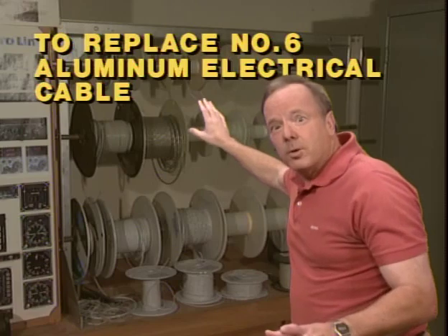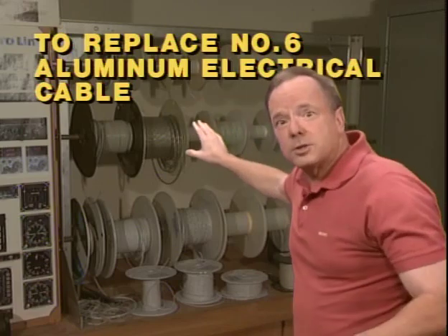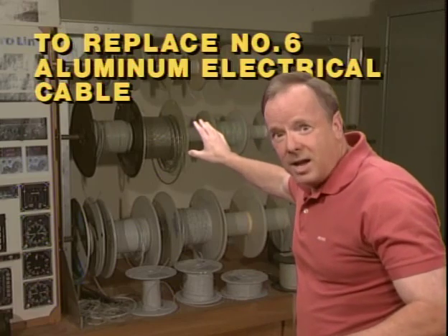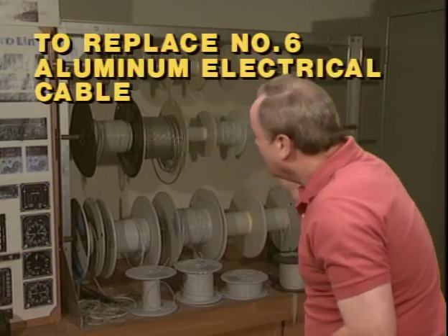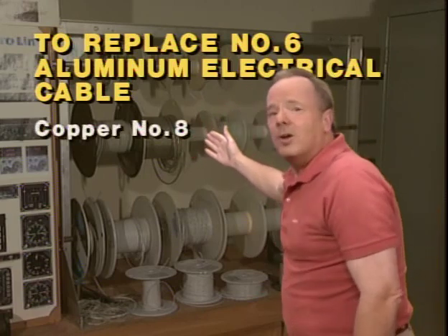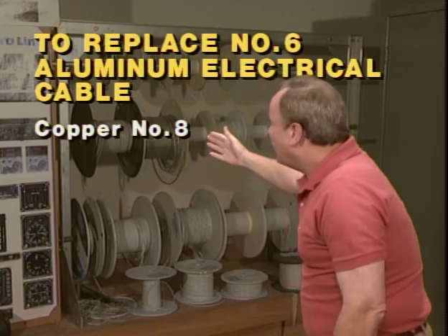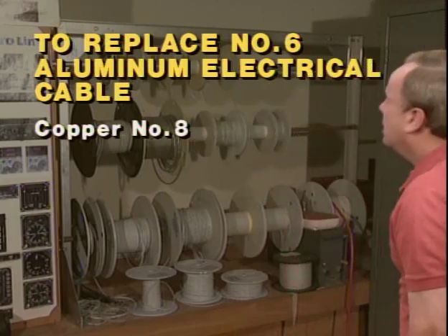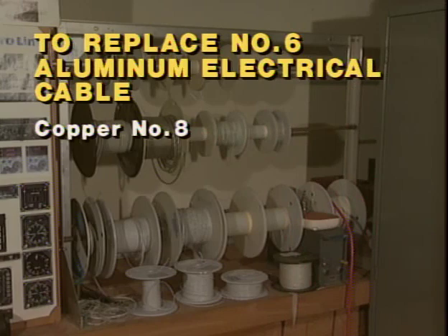Now, if you remember, you get to go 2 sizes smaller. That means you go up in gauge 2 sizes. So what gauge would it be? You've got it. It's copper number 8. So you've got it figured out. You can replace aluminum with copper, and you get to go up 2 gauge sizes when you do it.